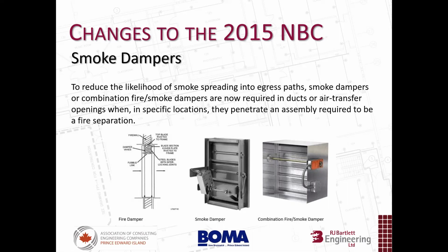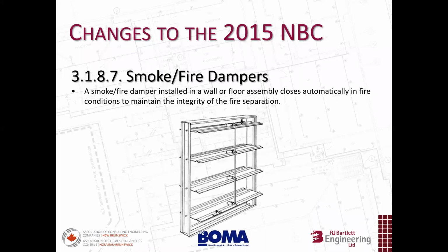Okay, so the next topic is smoke dampers. Smoke dampers have been introduced to the 2015 code to reduce the likelihood of smoke spreading into egress paths. Smoke dampers, or combination fire smoke dampers, are required in ducts and air transfer openings when, in specific locations, they penetrate an assembly required to be a fire separation. Some of these specific areas are public corridors, assembly occupancies, care occupancies, group Bs, and residential occupancies. So these dampers are designed to close automatically in fire conditions to maintain the integrity of the fire separation.